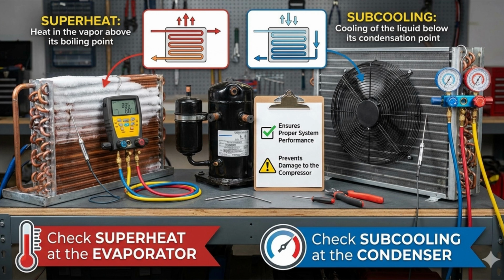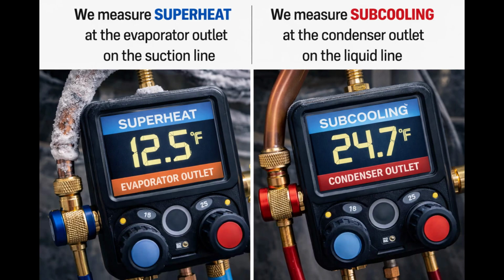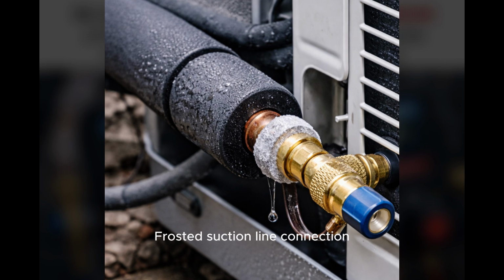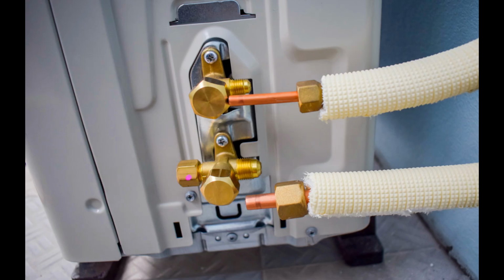As technicians, superheat and subcooling tell you exactly what the refrigerant is doing inside the system. They help confirm whether the system is properly charged, whether the expansion device is working, or if airflow issues are affecting performance. If you know both values, you can diagnose almost any refrigerant side problem without even opening a gauge or a pipe. We measure superheat at the evaporator outlet, specifically on the suction line, while we measure the subcooling at the condenser outlet, specifically in the liquid line.